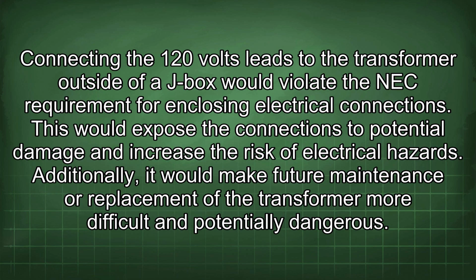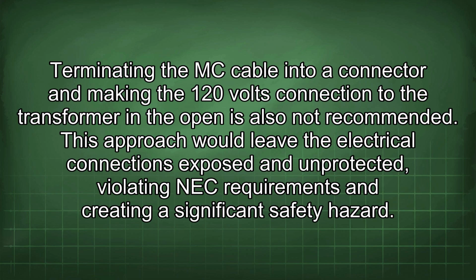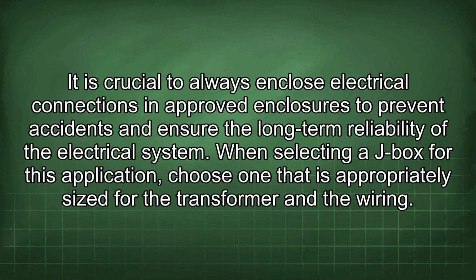This would expose the connections to potential damage and increase the risk of electrical hazards. Additionally, it would make future maintenance or replacement of the transformer more difficult and potentially dangerous. Terminating the MC cable into a connector and making the 120 volts connection to the transformer in the open is also not recommended. This approach would leave the electrical connections exposed and unprotected, violating NEC requirements and creating a significant safety hazard. It is crucial to always enclose electrical connections in approved enclosures to prevent accidents and ensure the long-term reliability of the electrical system.